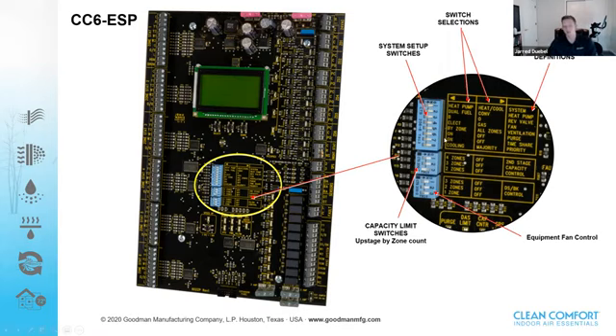So for example, if I have one zone that just finished up with a heating call and then a cooling call comes in, well, if I have the purge on, then I'm going to go ahead and for 60 seconds purge all that heated air out of the ductwork into the zone that was calling for heating before I switch over to cooling and start conditioning the cooling space.